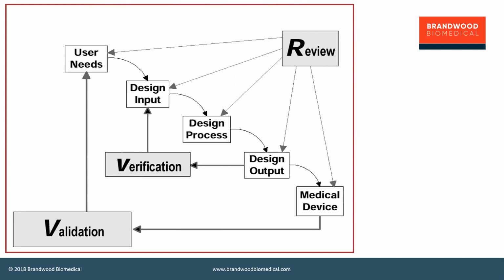And they also all need to have a mechanical design that's going to be safe. They're going to need to be strong enough to do the job. The first 2 of those, the problem is the same for every device in the series. If a laboratory turns out 100 of them over a year, they still need to be biocompatible. They still need to be sterile. But the mechanical design is different for each one because they are each one individually manufactured to fit an individual patient. And so there you have a somewhat different challenge in validating for the individual user.